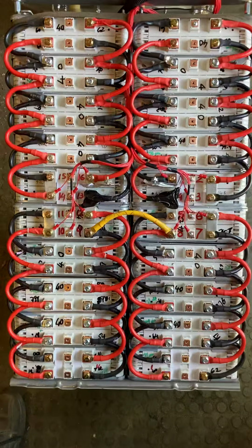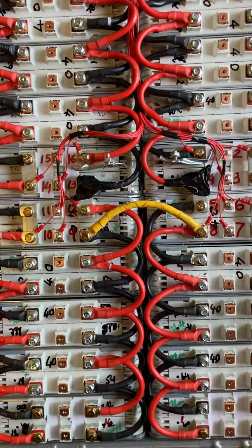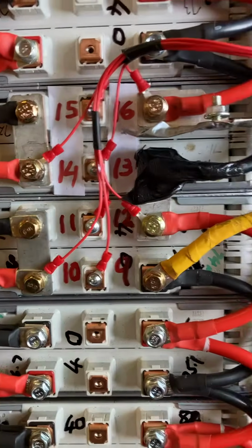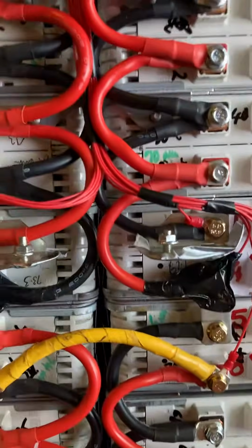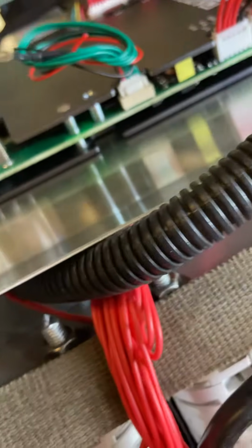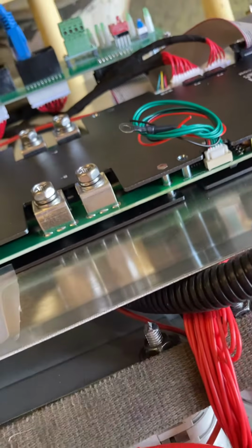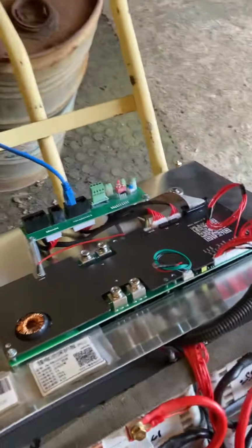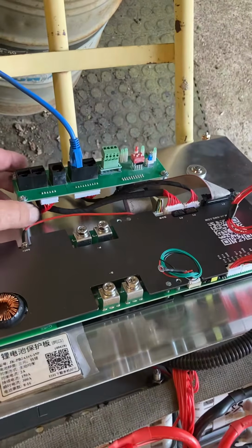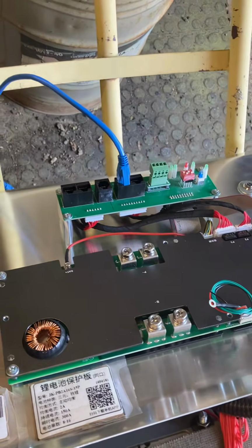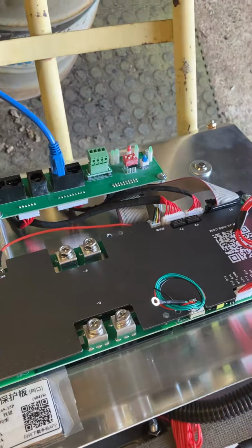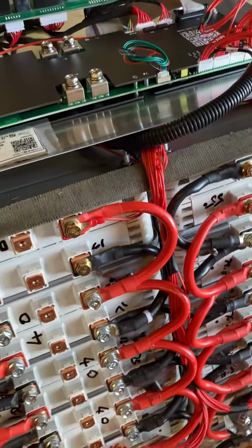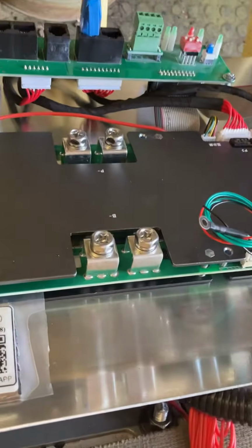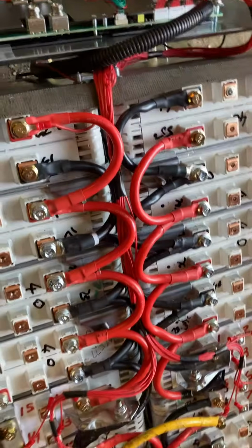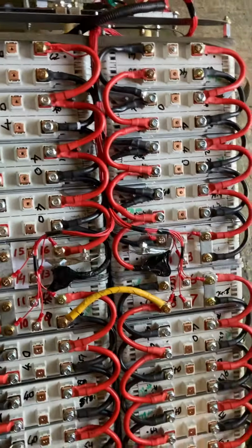Next step completed. I've got all the BMS wiring sorted - 16 connectors this side, 16 connectors this side, all feeding back up to the BMS here. The temperature senders that feed down the back still need to be put in position, but I've got the BMS mounted solidly, and the communications board mounted so it's possible to get to the connections behind. Now I've got to put the battery minus up to the BMS, and then we're ready to go live and give it a test.